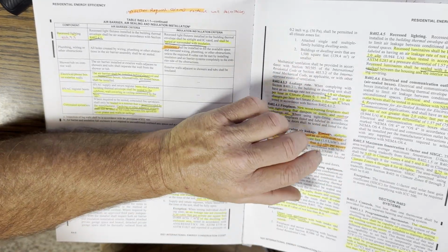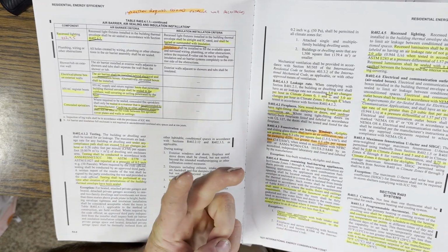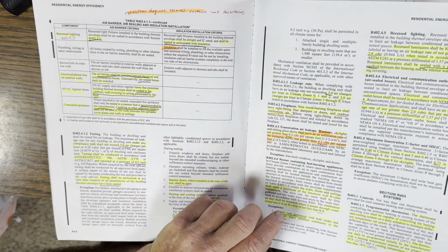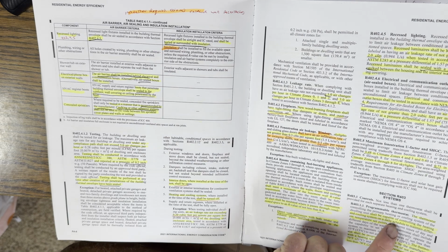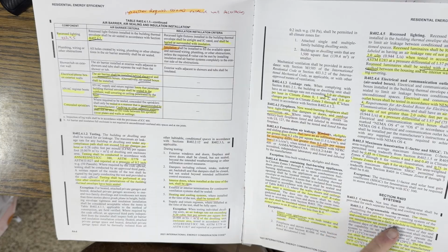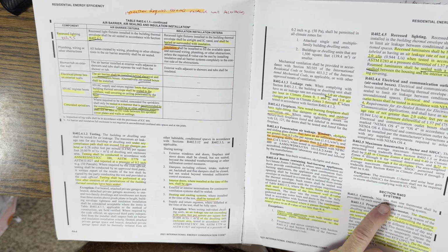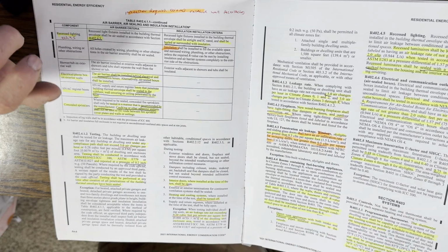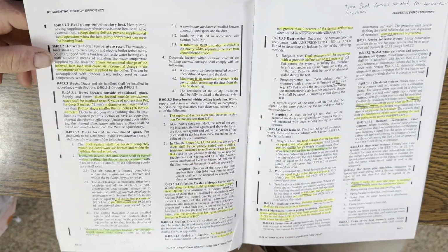the new addition is going to have its own furnace and its own programmable thermostat. So there's two answers for the own furnace. One was an analog type, old style thermostat. The other one was a programmed one, capable of controlling the heating and cooling system on a daily schedule. Anyway, the point is the thermostat had to be digital and programmable. And right here it says not less than one thermostat shall be provided for each separate heating and cooling system. So those are your answers that led to this answer for that particular question.